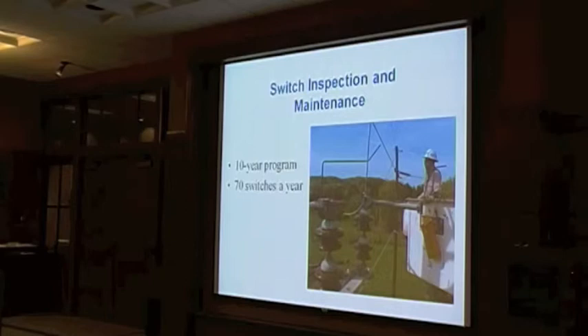But you have to have that separation so that no current would want to jump from this device when closed down into the structure itself. A 10-year program again, there's about 700 switches on the system, so we're going to try to get about 70 switches a year. They are inspecting, as he's doing here, but they'll also lubricate it with a graphite lubricant. They'll operate it and make any adjustments to make sure that when we come out there and we need to use that switch, it's going to function properly. So this is a preventive maintenance program, of course.